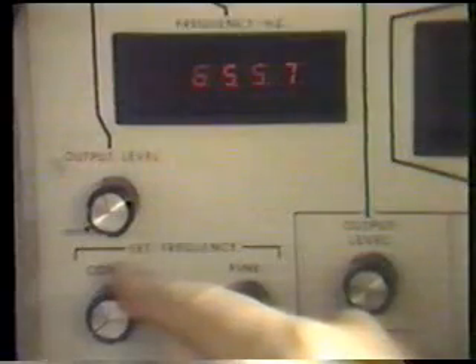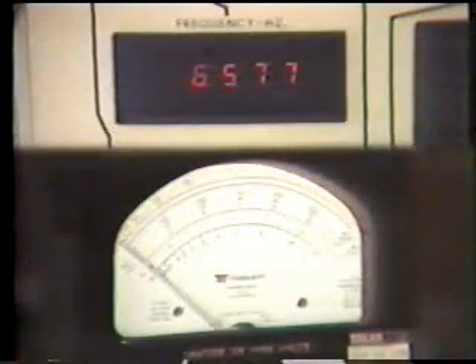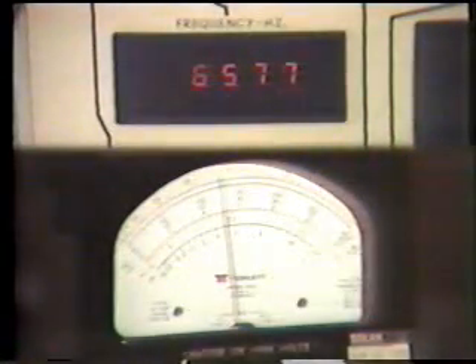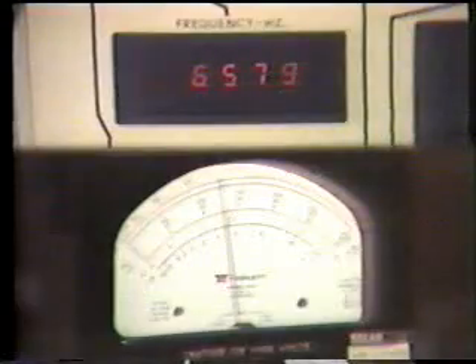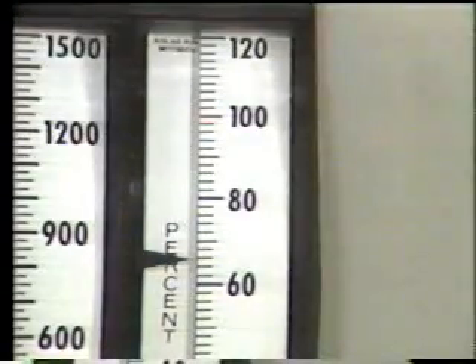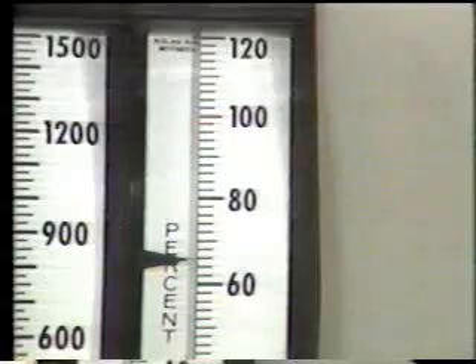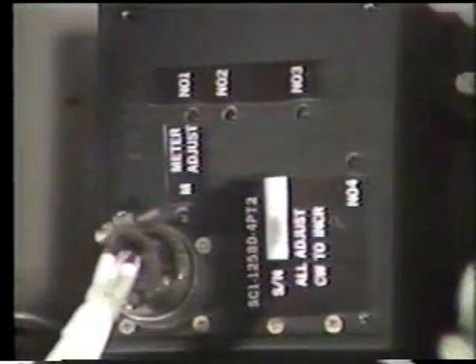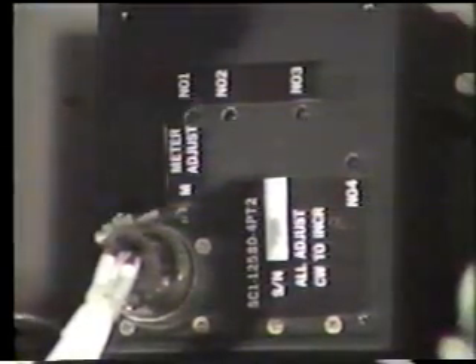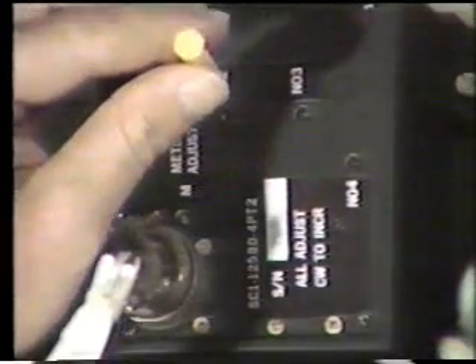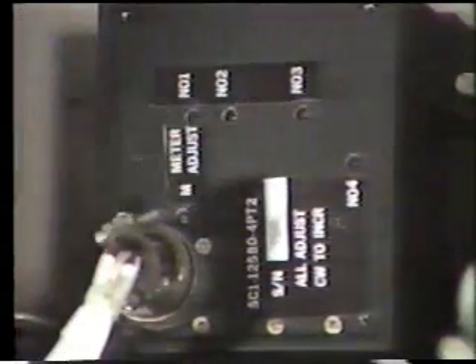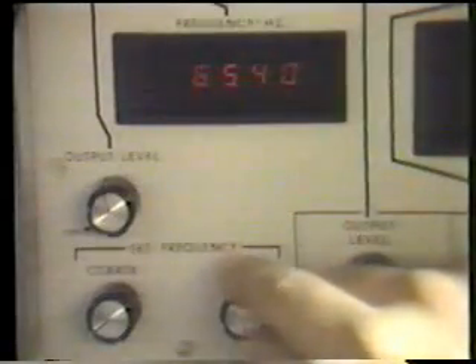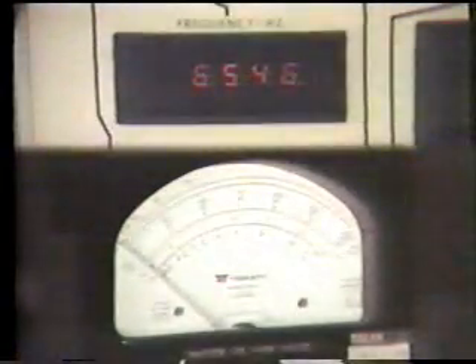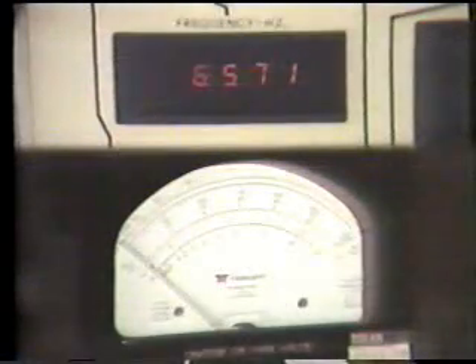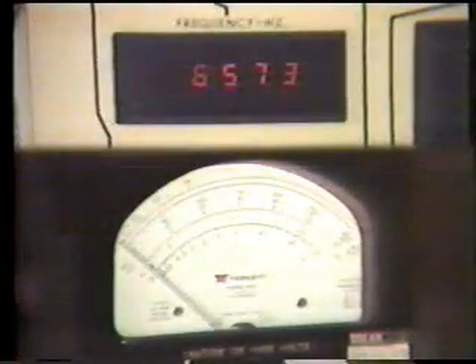Slowly increase the signal generator frequency to the set point value. Observe the switch contacts transfer as indicated on the VOM. Check the speed meter. It should read 66% speed. If the switch does not transfer at the correct frequency, adjust pot number 2. Decrease and slowly increase the signal generator frequency until the correct set point is reached. Again, the tolerance is plus or minus 30 Hertz.